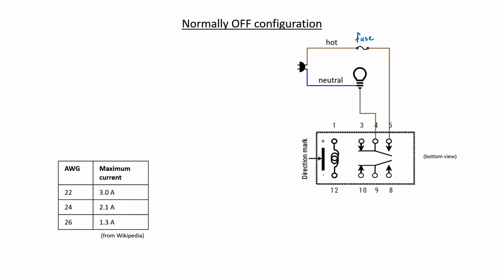We know that in Singapore we have 230 volts RMS coming out of the wall. If we know the wattage of our light bulb, we can calculate how much current will pass through both the fuse and the relay when the hot side of the circuit is turned on. For example, if we use a 60-watt light bulb, that means 261 milliamps of current will pass through our fuse and relay. If we instead use a 100-watt light bulb, then 435 milliamps of current would pass through.